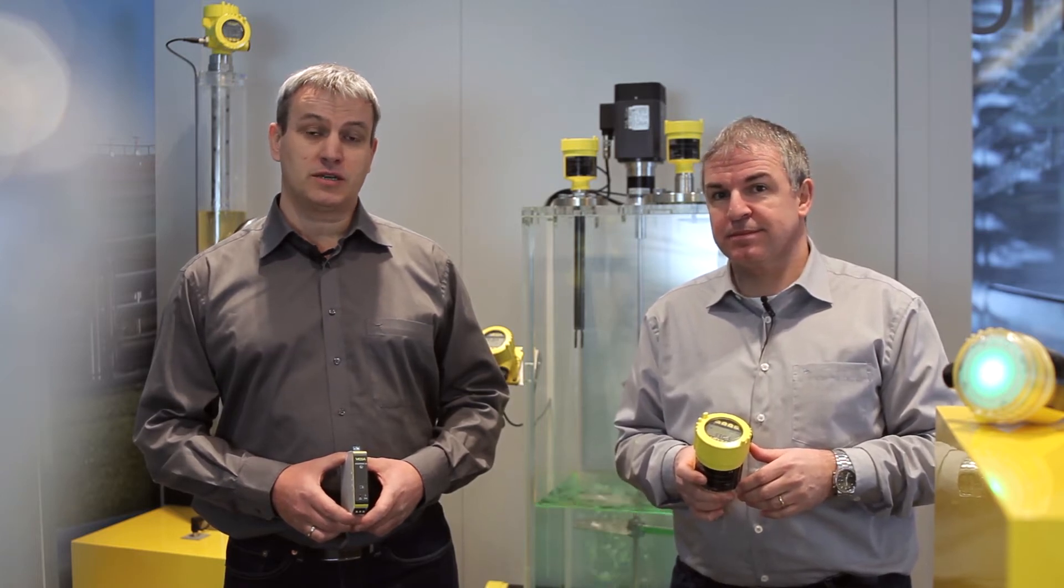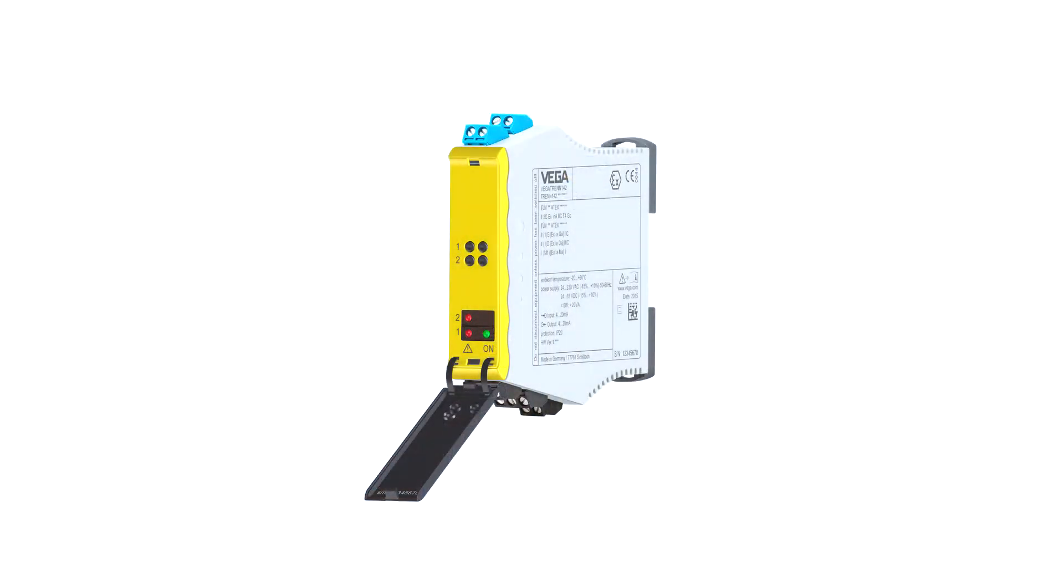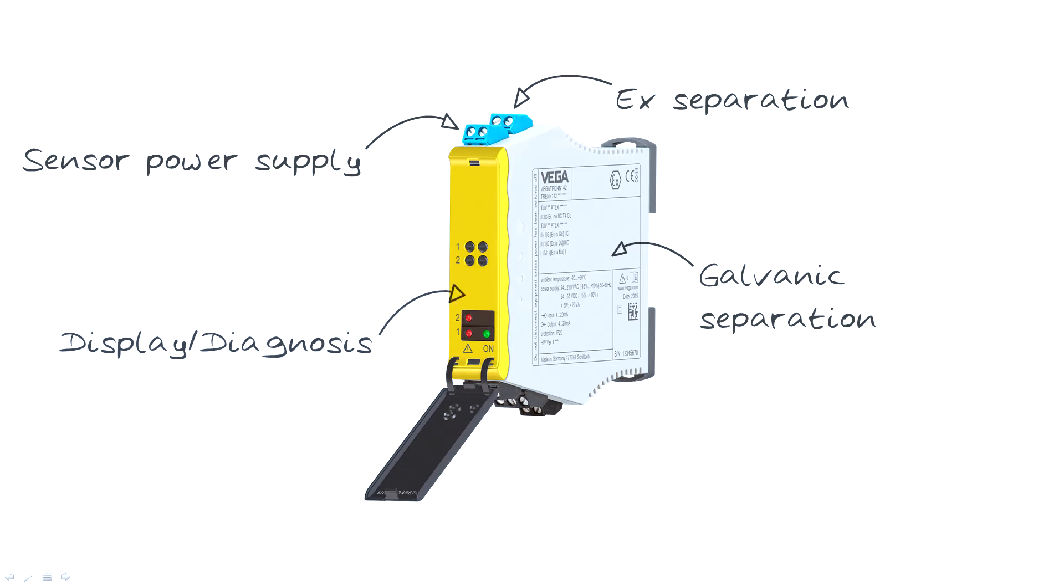First, let's have a look at the task of a separator. First of all, it can supply the sensor with power and in case of hazardous areas it can also be used as an EX separator. The inputs and outputs as well as the supply voltage are galvanically isolated. The instrument also provides local display and diagnostic options.